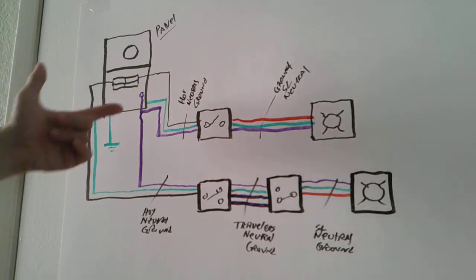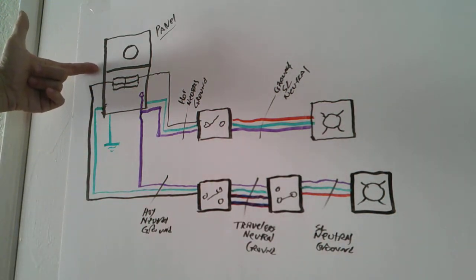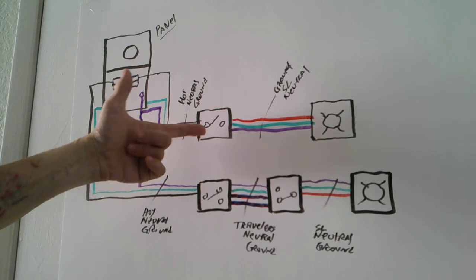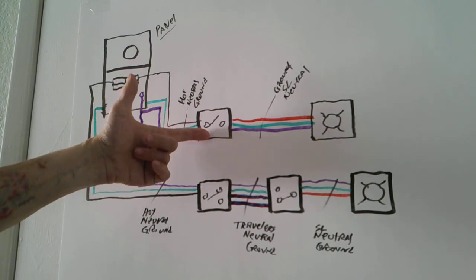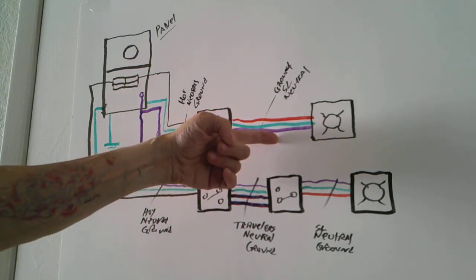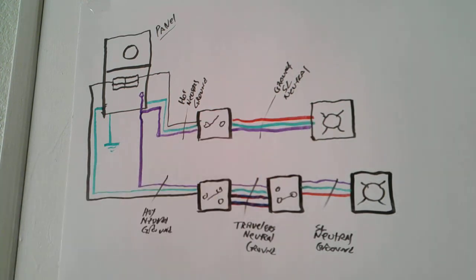You always want to start at the power source. Then you want to move to the group of wires that's feeding your device or your control device. And then you want to go to the group of wires that's going to your device that's being controlled.